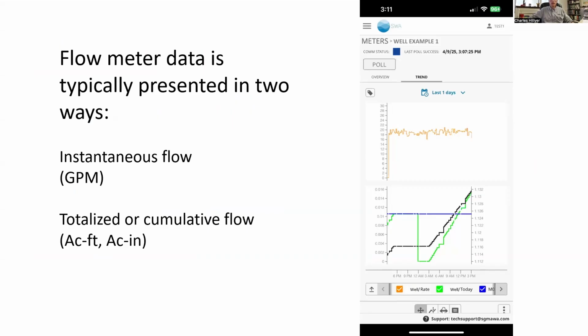This was the same thing that the Sigma Water Analytics people presented. And I want to highlight it again here because this chart, this graph, or this image in particular shows the two different ways that we look at flow meter. Here you can see the instantaneous flow rate. And over a period of time where the flow rate's not changing significantly, you should expect to see the flow rate look like this. It's more or less flat, but there's a little bit of noise in the data. You can never make the noise go away completely because there's always noise associated with any sensor measurement. But it should be relatively flat.